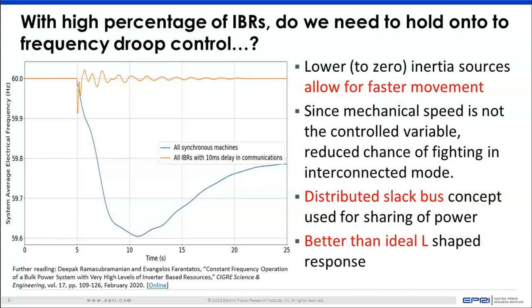But with inverters, because they are so fast, you can actually shorten the time of that primary frequency control region to almost zero. And in this case, when you have all inverters in the system, using a concept which is similar to distributed slack bus, where if you solve a power flow with a distributed slack bus, you're essentially saying that not all the losses and the load is going to be put upon just one single machine, but it's going to be distributed across multiple inverters.